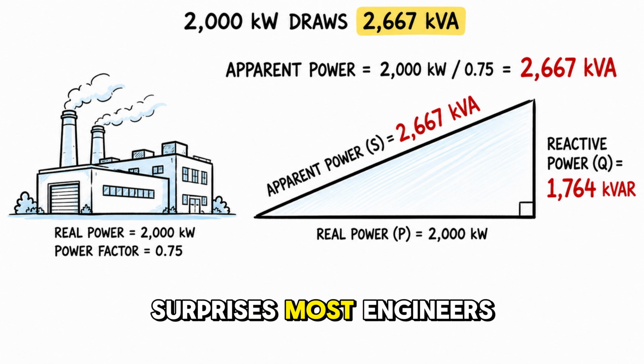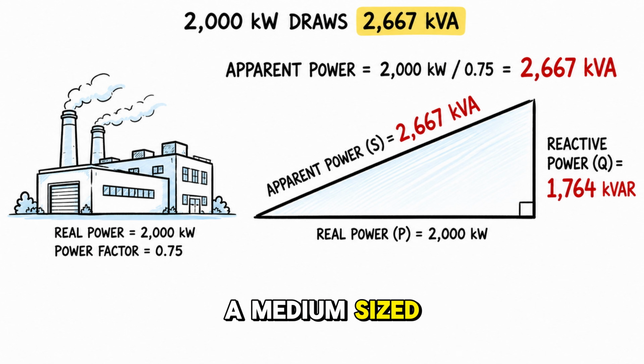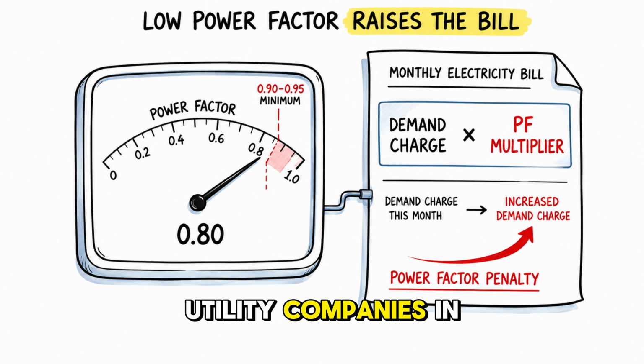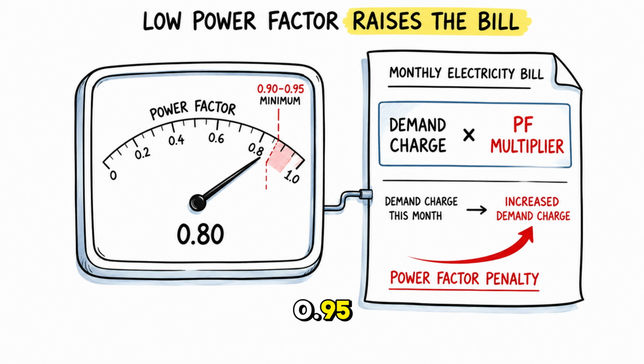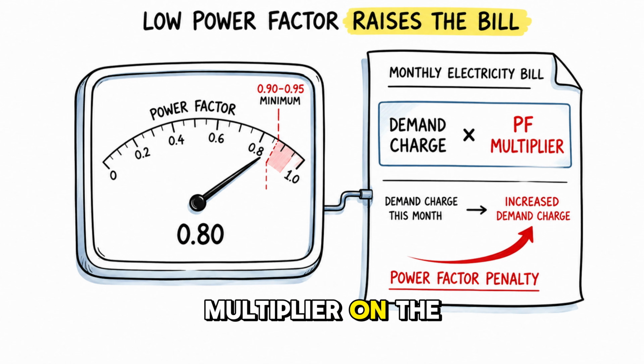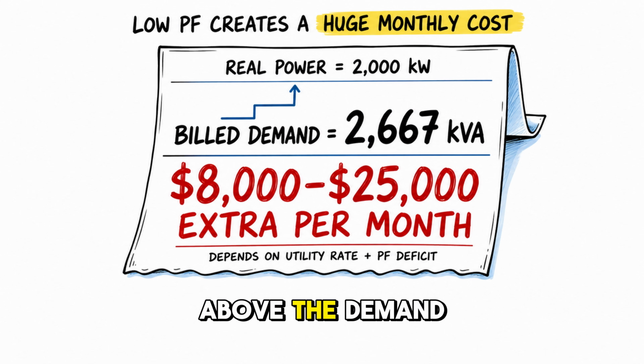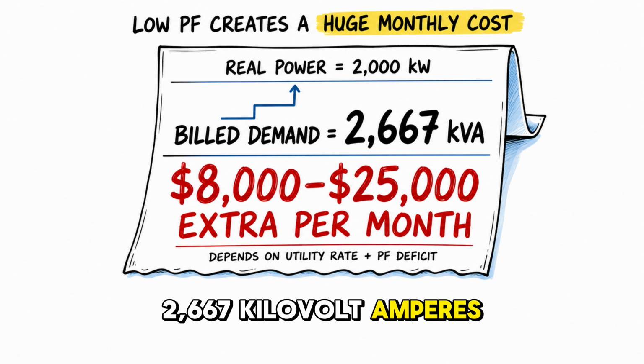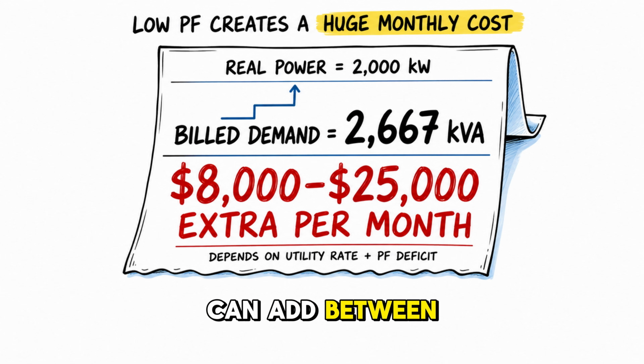Here is a real number that surprises most engineers when they first see it. A medium-sized manufacturing facility, drawing 2,000 kilowatts of real power at a power factor of 0.75, is drawing 2,667 kilovolt amperes of apparent power. The reactive component is 1,764 kilovolt amperes reactive. Utility companies in most states charge a power factor penalty once power factor drops below 0.9 or 0.95. This penalty is typically applied as a demand charge multiplier on the monthly electricity bill. For the facility above, the demand charge on 2,667 kilovolt amperes, instead of 2,000 kilowatts, can add between $8,000 and $25,000 to the monthly electricity bill, depending on the utility rate structure and the severity of the power factor deficit.